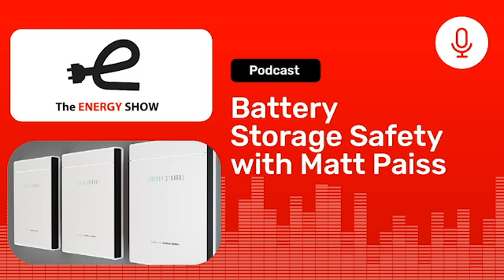If you have a system with a number of different batteries, you might have an energy storage system manager, which takes the data from all of those BMSs and ensures that the different containers or enclosures are operating appropriately. There might be fire protection equipment on these larger systems, and some components the energy storage management system communicates with. In the case of a utility or larger system, all the data might be monitored off-site, at what's typically called a SCADA facility that monitors the controls. Even residential systems communicate with the manufacturer or the integrator who installed it, just to make sure any alarms are noted by personnel.